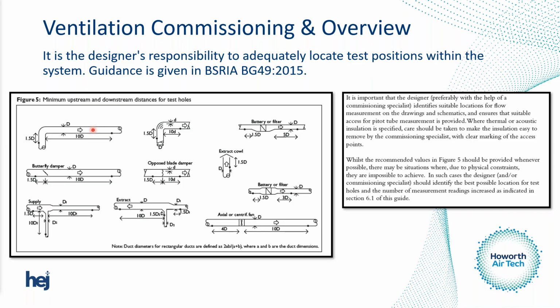One of the first things that I do as a project is reaching validation stage and completion is ask for the commissioning data of the system. And you can tell usually from looking over the pitot traverse readings and static pressures if the test position is in an adequate position.